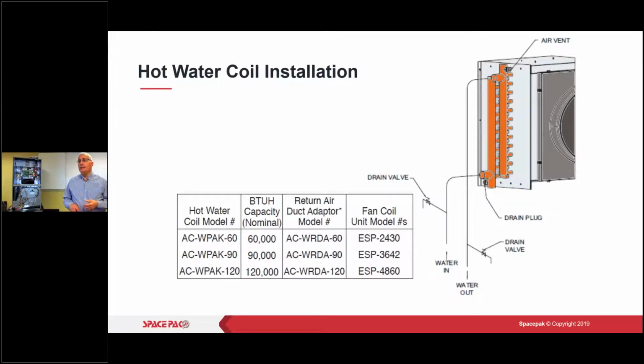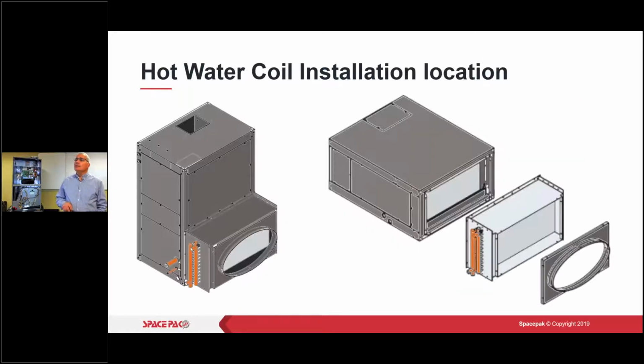Okay, so here's our hot water coil installation. As you can see, there's your nominal input. There's the coil numbers. Water in, water out, pretty simple. Again, always make sure that if it could be in a freeze up condition that you treat that properly. The coil is on the return side of our air handler. Here we're showing you in a horizontal fashion or in a vertical fashion. So it comes back on the return side.